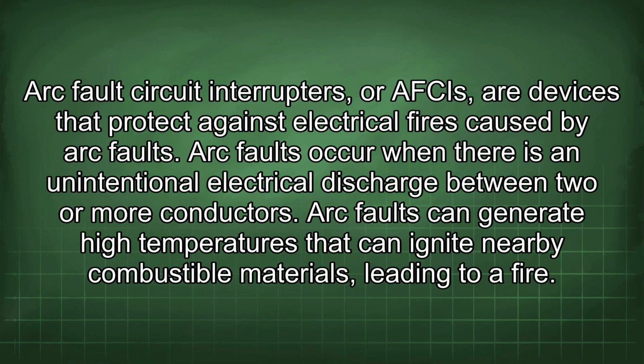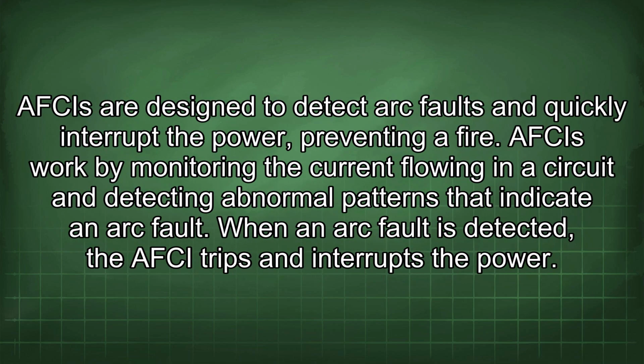Arc fault circuit interrupters, or AFCIs, are devices that protect against electrical fires caused by arc faults. Arc faults occur when there is an unintentional electrical discharge between two or more conductors. Arc faults can generate high temperatures that can ignite nearby combustible materials, leading to a fire. AFCIs are designed to detect arc faults and quickly interrupt the power, preventing a fire.